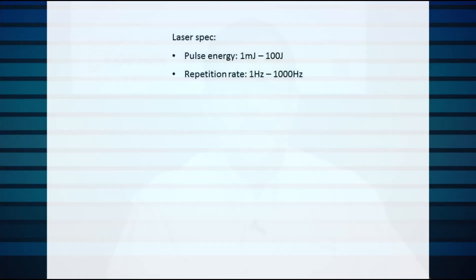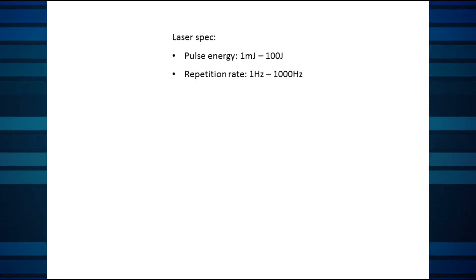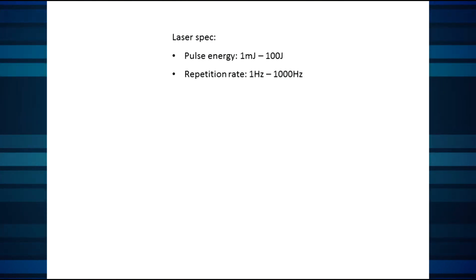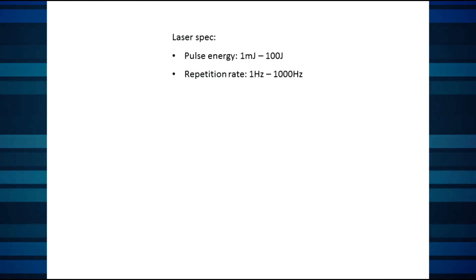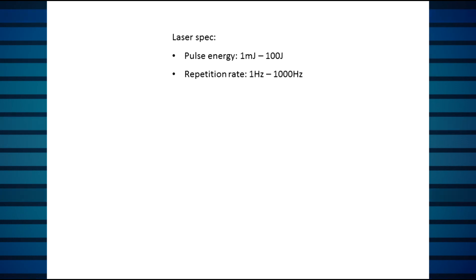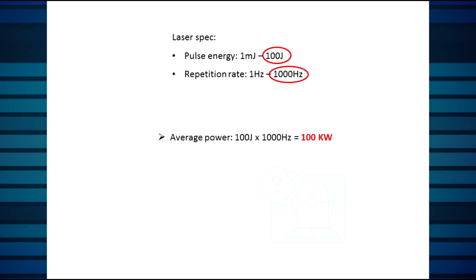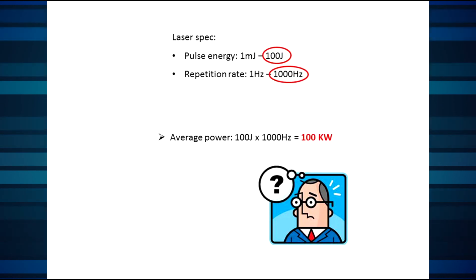We need to measure the laser beam and choose the right sensor. Here's where the fun begins. If the laser spec says pulse energy 1 mJ to 100 J and pulse rate 1 Hz to 1000 Hz, we might look for a sensor that can handle all of those numbers. But wait — 100 J pulses at 1 kHz means the average power is 100 kW. If that's not really your beam, you've fallen into the worst-case combination trap.